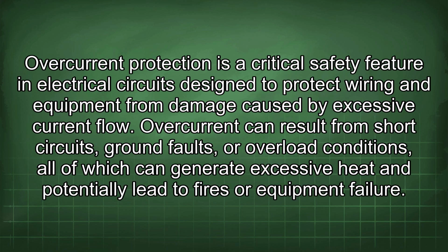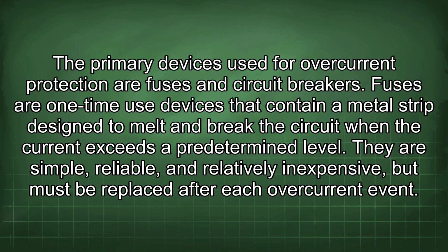Overcurrent protection is a critical safety feature in electrical circuits designed to protect wiring and equipment from damage caused by excessive current flow. Overcurrent can result from short circuits, ground faults, or overload conditions, all of which can generate excessive heat and potentially lead to fires or equipment failure. The primary devices used for overcurrent protection are fuses and circuit breakers. Fuses are one-time use devices that contain a metal strip designed to melt and break the circuit when the current exceeds a predetermined level. They are simple, reliable, and relatively inexpensive, but must be replaced after each overcurrent event.